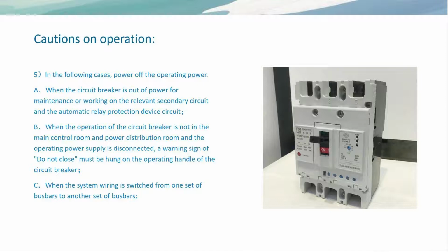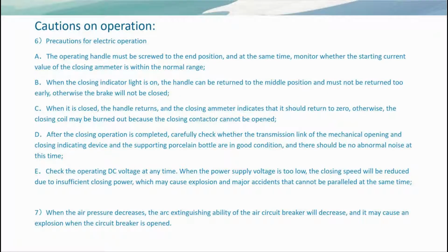B. When the operation of the circuit breaker is not in the main control room and power distribution room, and the operating power supply is disconnected, a warning sign of "do not close" must be hung on the operating handle of the circuit breaker. C. When the system wiring is switched from one set of bus bars to another set of bus bars. 6. Precautions for electric operation.